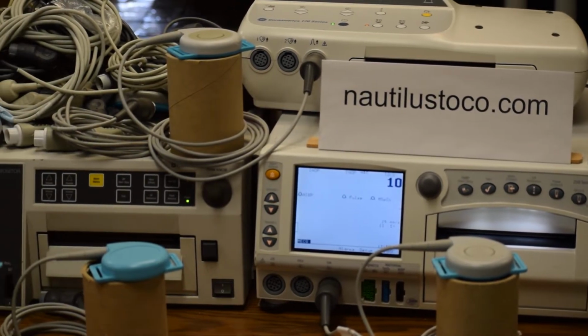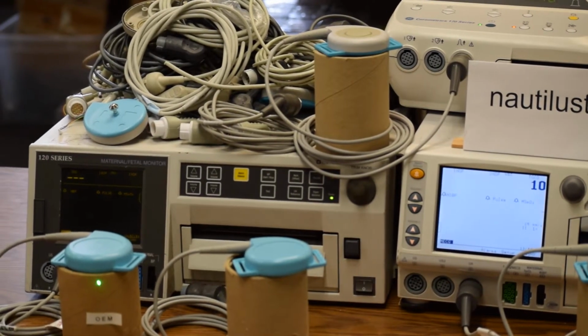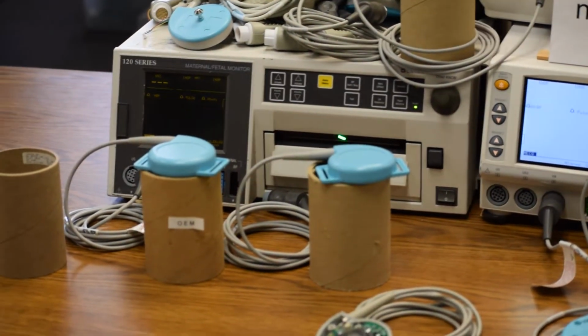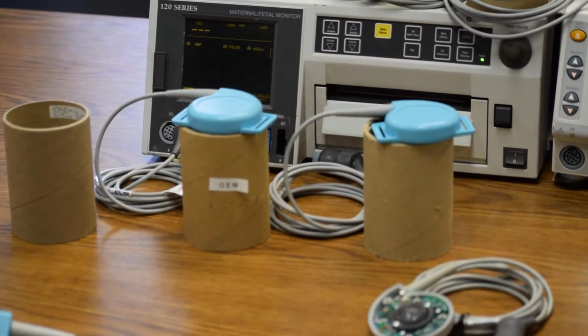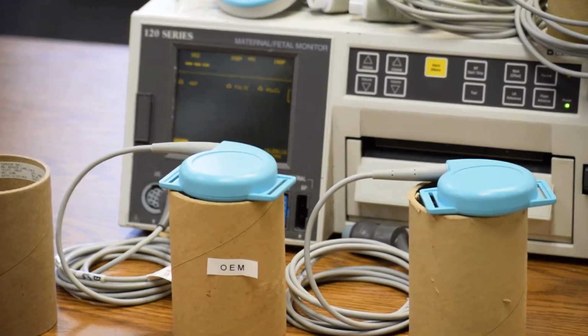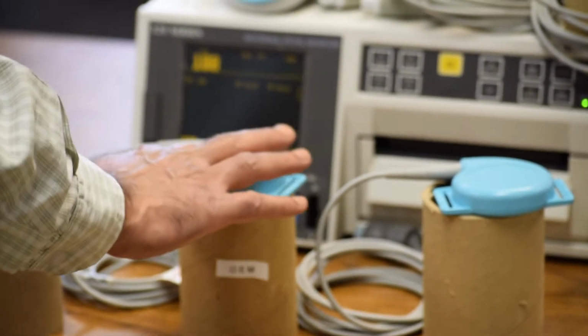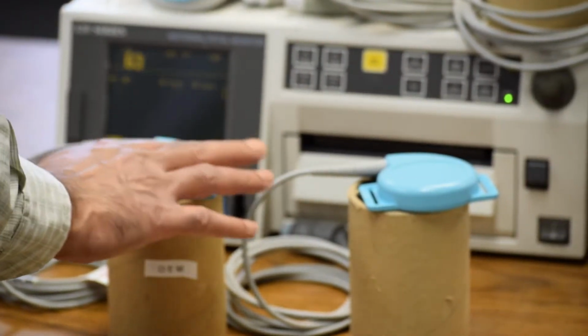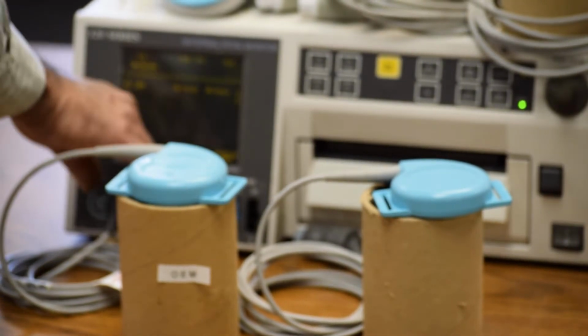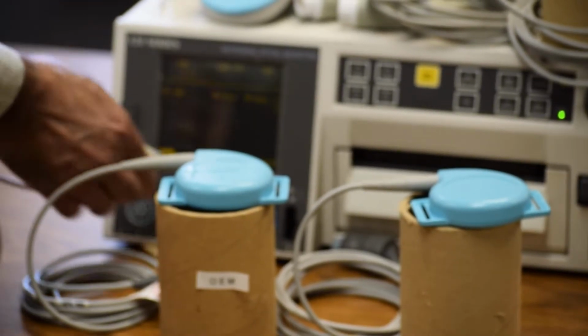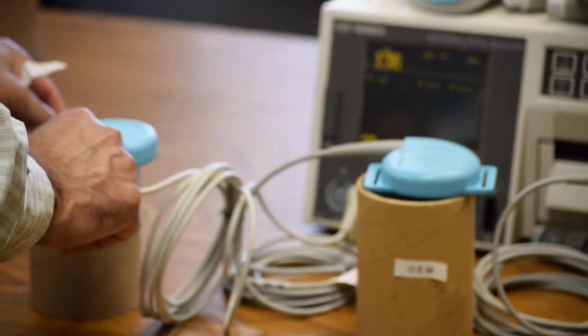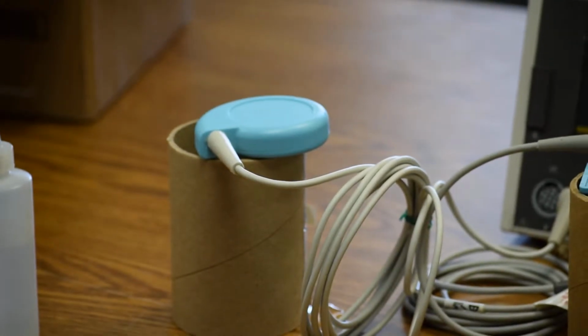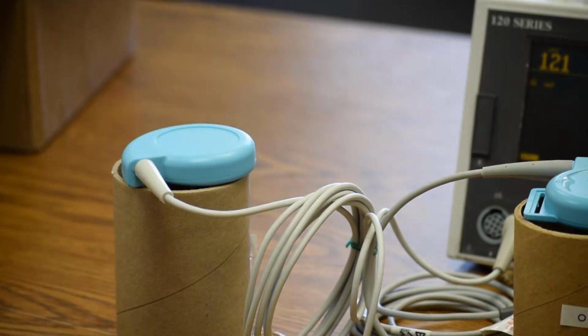Let us do a simple test comparing with genuine GE transducers connected to the 120 series monitor that you see. There are two 100% original GE transducers with GE labels. Let's test them and compare. Let us not change the volume setting. Take out original transducer. Let's put this non-OEM transducer, same plug, same settings. See the very low echo volume, because sensitivity of crystals is completely damped because of the silicone used.